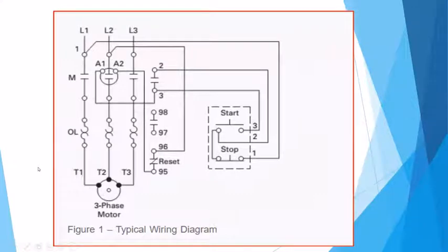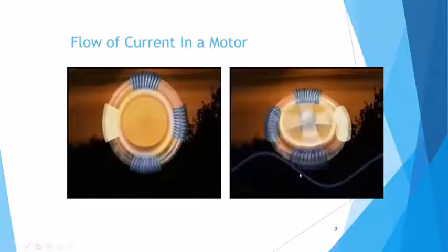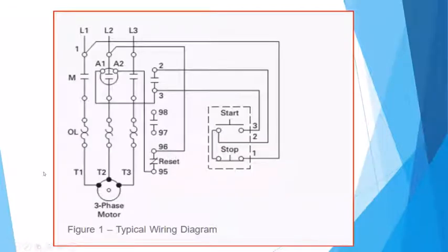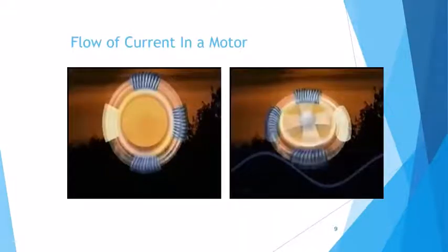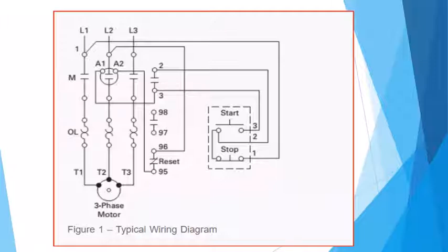The issue, the difficulty, is this: because of the 60 cycle power, and let's say it's a 480 volt source or 240 volt source, the motor, because it's not up to speed, before that rotor starts turning, it's just a resistance. So the current that can flow, when you just turn it on straight with a set of contacts, can be anywhere between 3 to 6 times the value. So let's say you have a 100 amp motor, it can take 500 amps to start it. That then drives your requirement for generators, power lines, transformers, everything else.